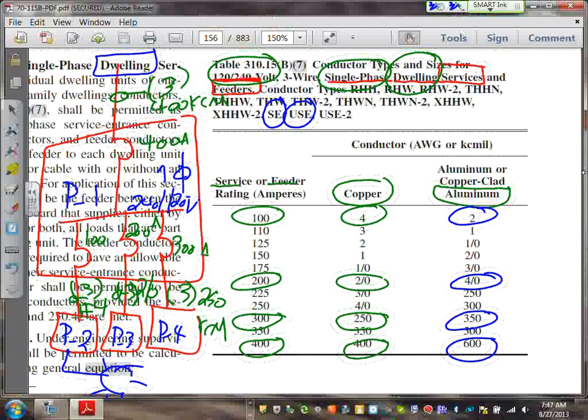I'm going to tell you from now on, for the building that we have, I would like you guys to use conduits and wires. We're going to bring a conduit to this building, PVC conduit, fill it with the exact wires like this, 400 KCM, if it's the same size. We're going to take an EMT conduit from this box to this box, and we're going to fill it with these particular wires. So we're going to use conduits. Why conduits? We're engineers. Conduits are better protection than SE cables. Where would I use SE cable? Cheaper. Okay, so if it's an engineer department, might as well use conduits, EMT conduits. What's EMT conduits? You're looking at it right in that type of conduit, except it's going to be a little bit bigger to handle these conductors.